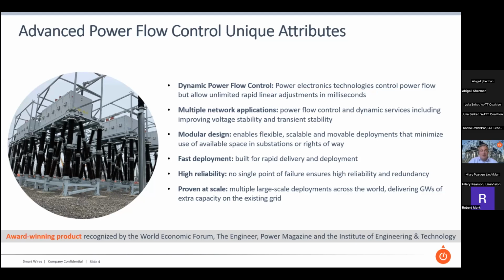You can do an unlimited number of changes and movements of that adjustment to the power flow control, and you can do it in milliseconds. So it's very fast, very controllable, and not restricted by mechanical actions, so you could use it throughout the whole of the year as a result.